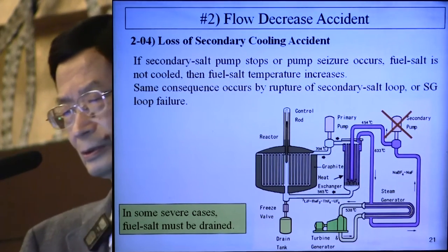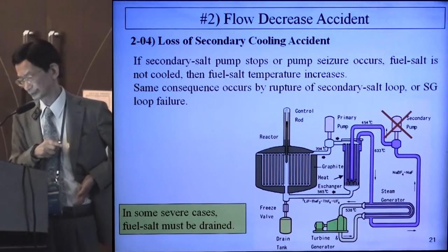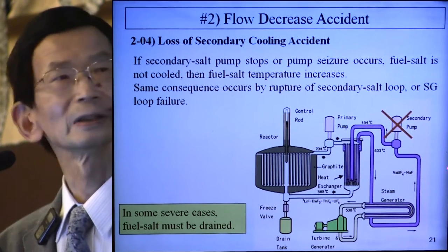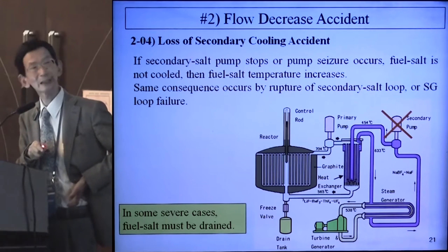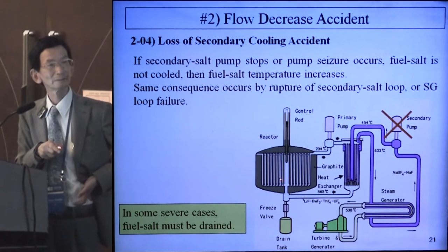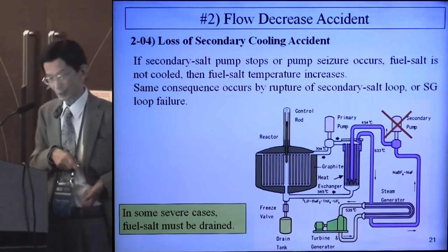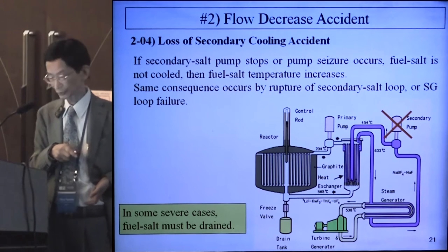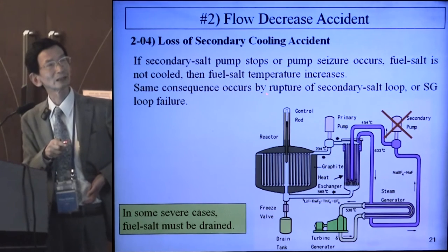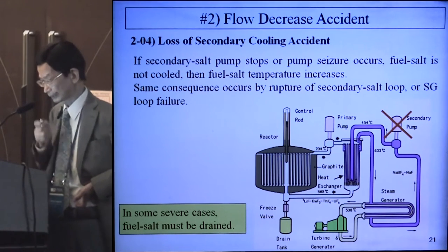2-04 Loss of Secondary Cooling Accident. In normal operation, fuel salt and secondary salt are both circulating. If the secondary pump stops, the cooling function is lost and fuel salt temperature will increase. In some severe cases, fuel salt must be drained. The same consequence can occur by rupture of the secondary loop or by steam generator failure.